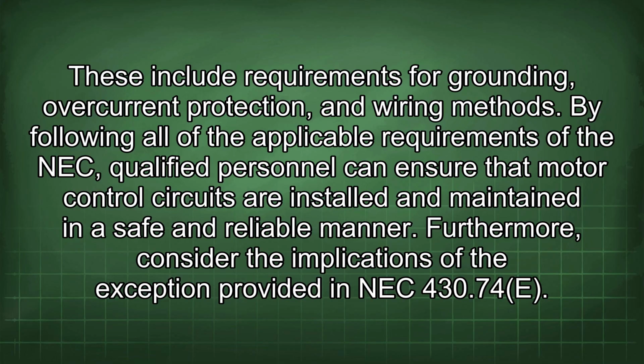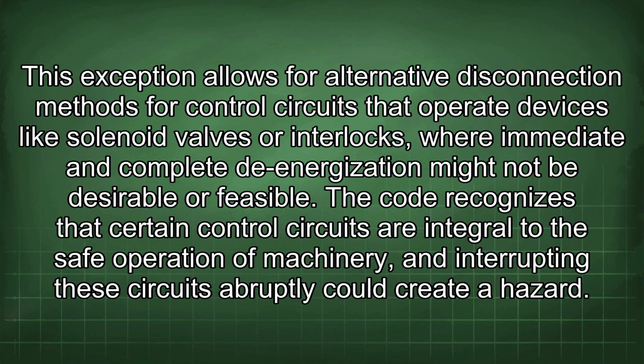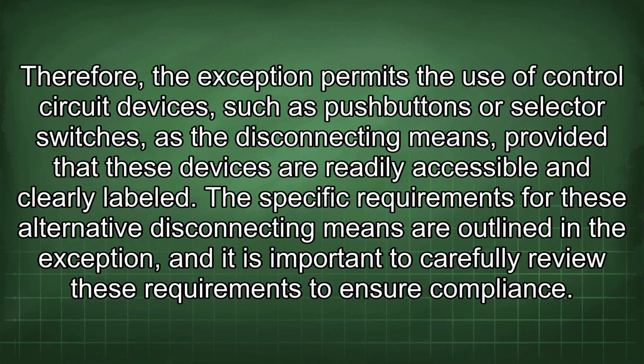Furthermore, consider the implications of the exception provided in NEC 430.74 E. This exception allows for alternative disconnection methods for control circuits that operate devices like solenoid valves or interlocks, where immediate and complete de-energization might not be desirable or feasible. The code recognizes that certain control circuits are integral to the safe operation of machinery, and interrupting these circuits abruptly could create a hazard. Therefore, the exception permits the use of control circuit devices such as push buttons or selector switches as the disconnecting means, provided that these devices are readily accessible and clearly labeled. The specific requirements for these alternative disconnecting means are outlined in the exception, and it is important to carefully review these requirements to ensure compliance.